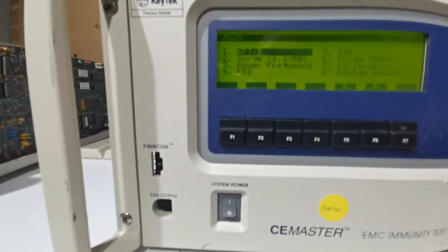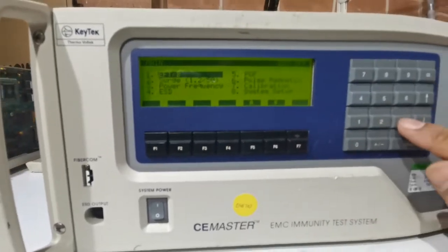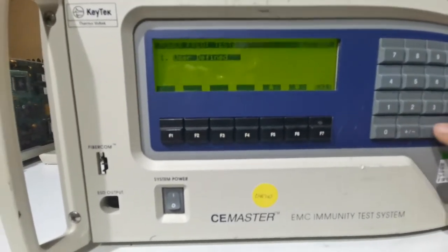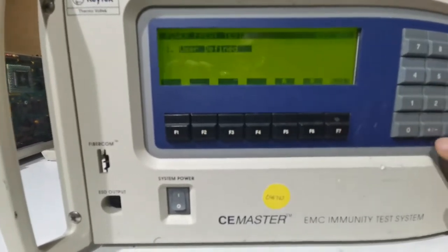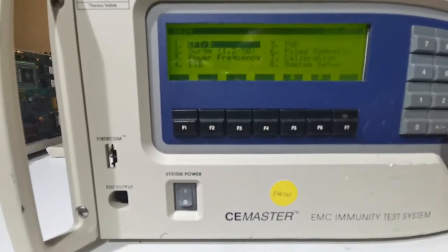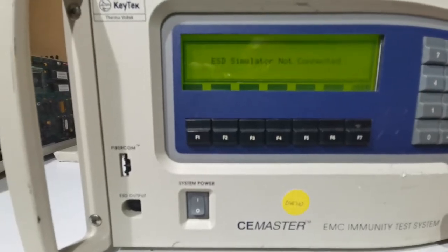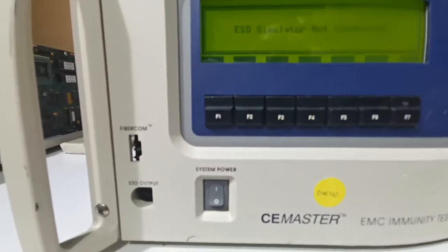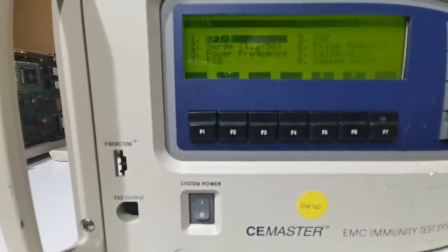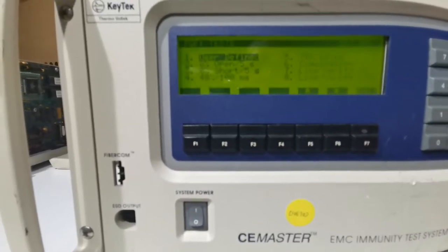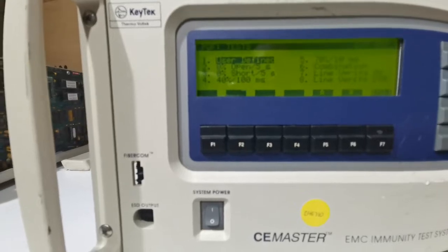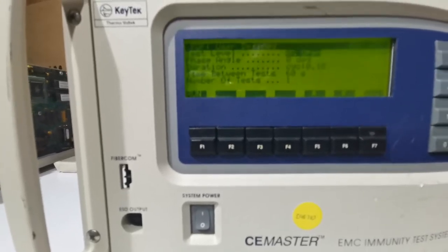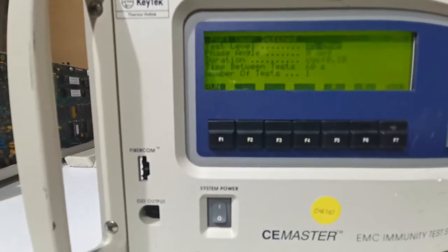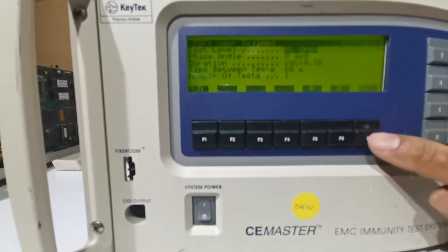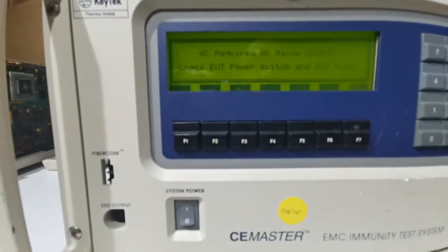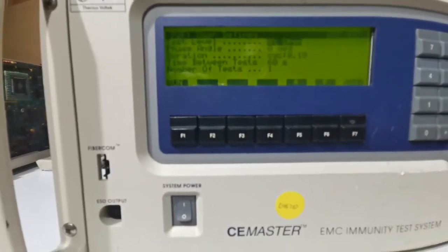Except number 3, which is power frequency, user defined. Yeah, perfect. That's working. And number 4, yeah, is the simulator not connected? I have that simulator, so that's all good. That's working. Number 5, which is voltage dips and interruptions, perfect. User defined. Yeah, you can set this one. Now if you run, it won't. It looks for the mains, so that's all good.